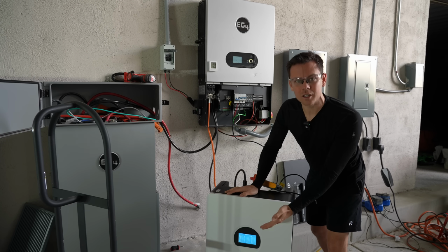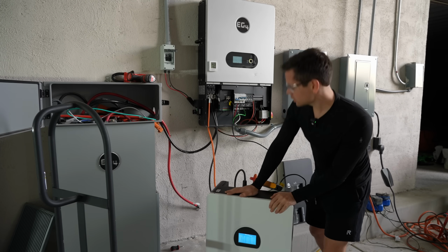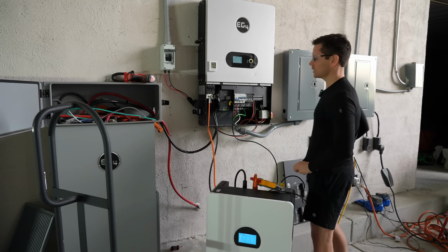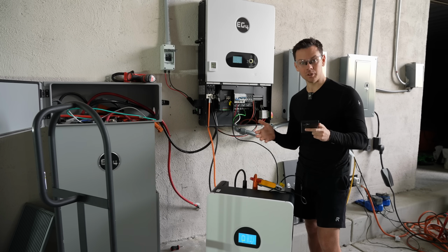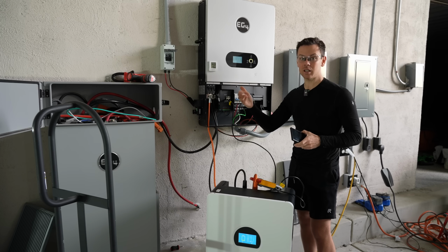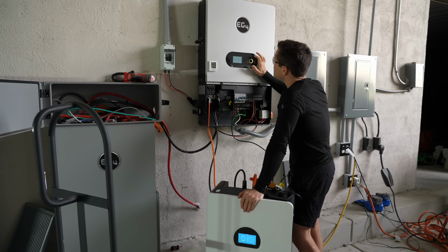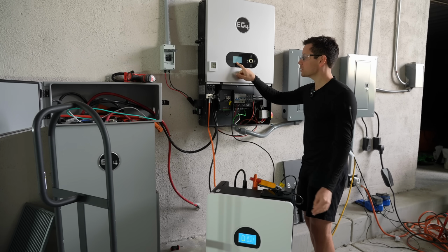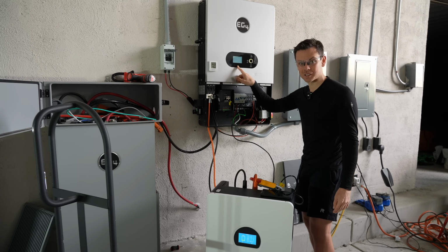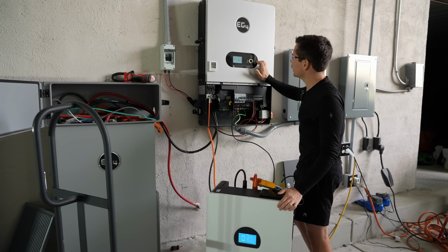But there's no error codes. It shows that it should be working. We've got warning 26, and that warning code is battery low voltage. Maybe we need to change the settings to change the cycling behavior. Here we go. Discharge cutoff state of charge is set to 15%. So we're gonna set that to 0, and it should work.